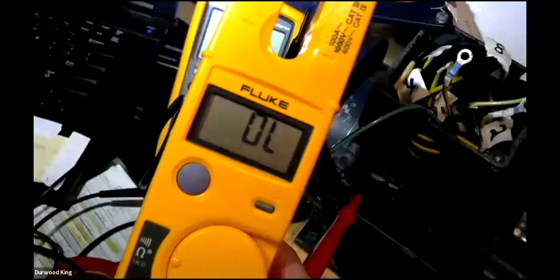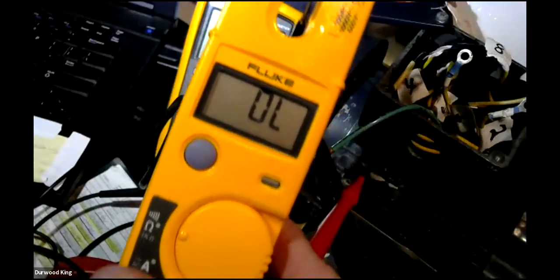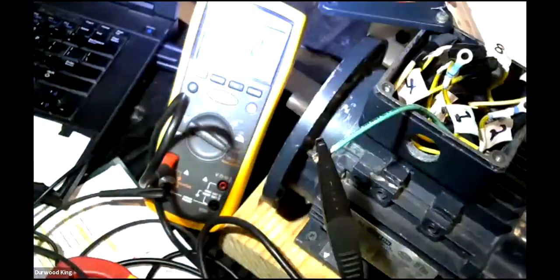See what I'm saying? With that meter you got on, do it between the phases. See if you got a phase going up. Say it again. With that T5 1000, do it between the phases 1, 2, and 3, and see what you get. Now, between the phases, you're going to read through the motor. Now, that's another subject. Now, let's hold that just for a second.